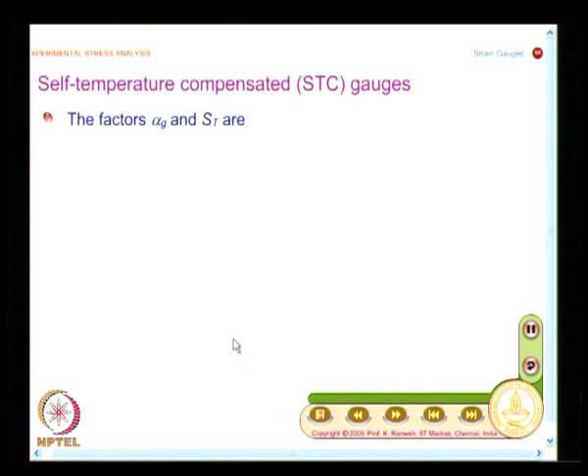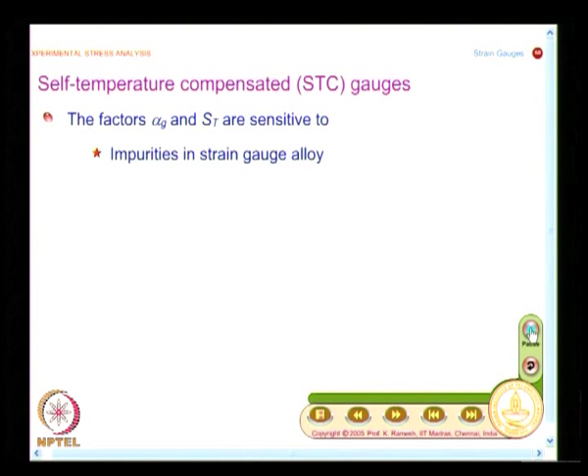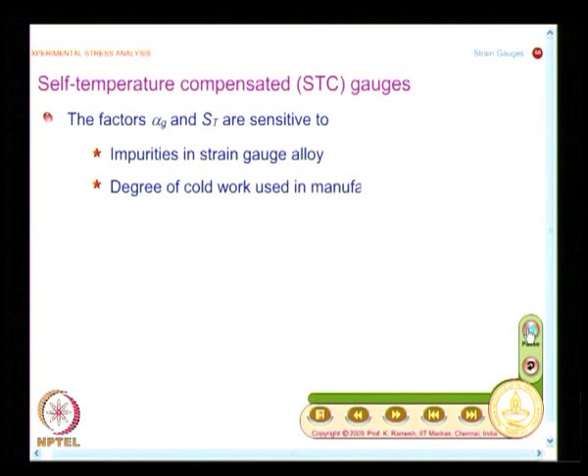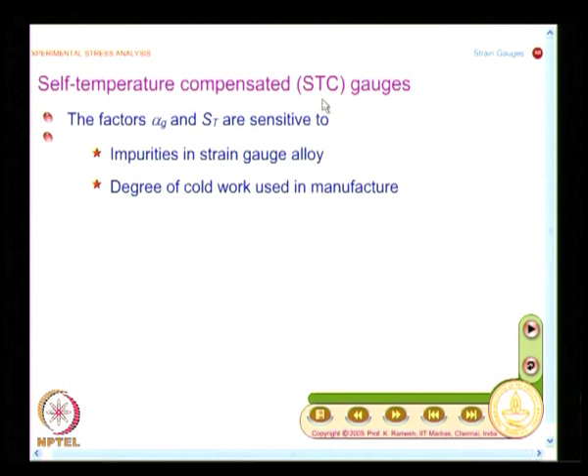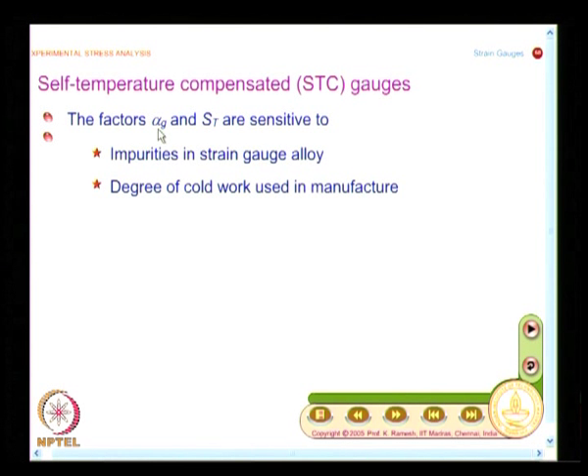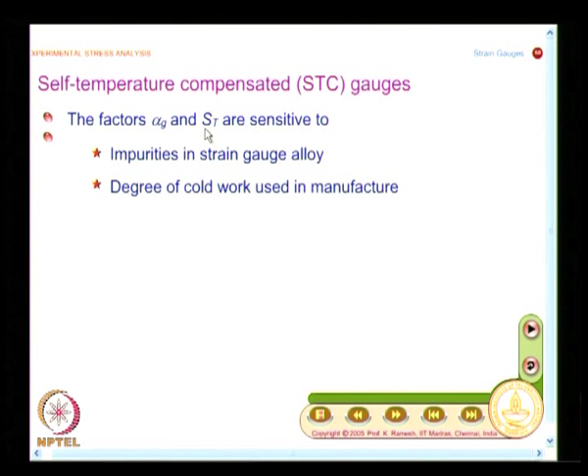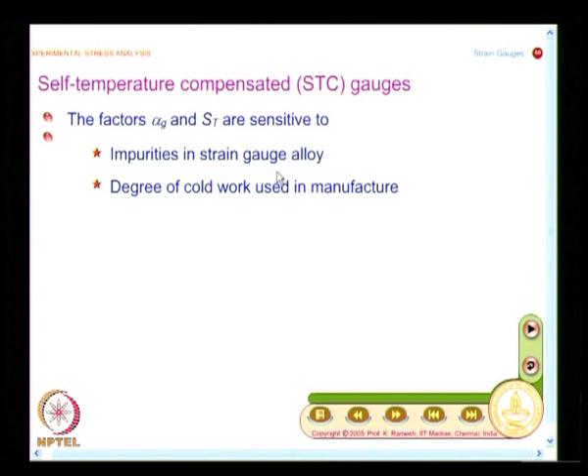First, we will take up how to get self-temperature compensated gauges — abbreviated as STC in the literature. Fortunately, the factors alpha_G (the coefficient of expansion of the gauge material) and the sensitivity of the strain gauge material for temperature change (S_T) are sensitive to impurities in the strain gauge alloy.